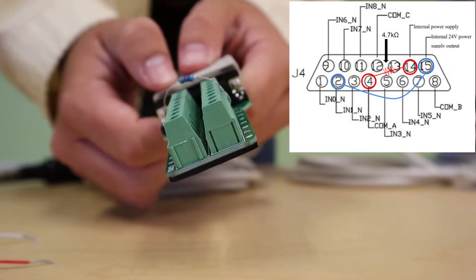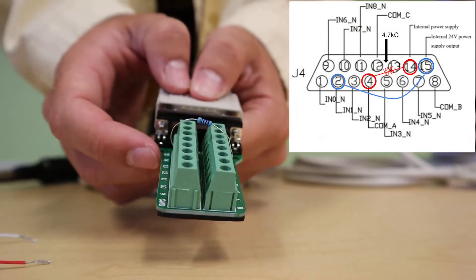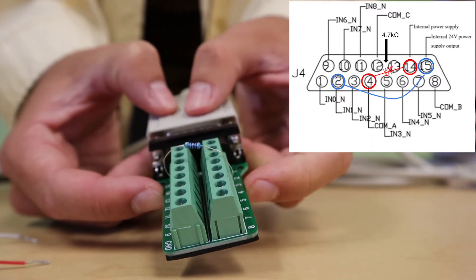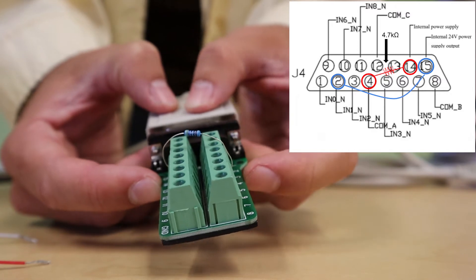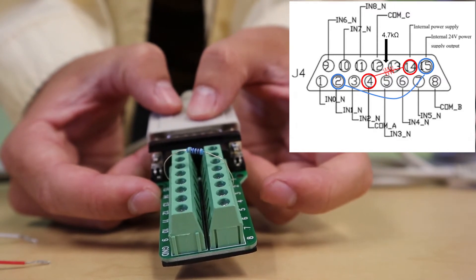We have to do something very similar for the inputs. We have to connect the internal power supply pin, which is pin 14 for the inputs, to our common for the input signals. COM A is pin 4 which relates to input 0, 1, and 2.